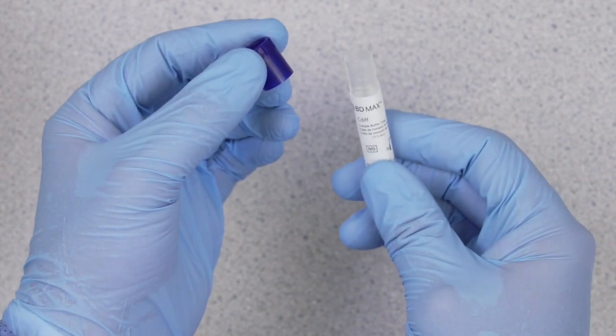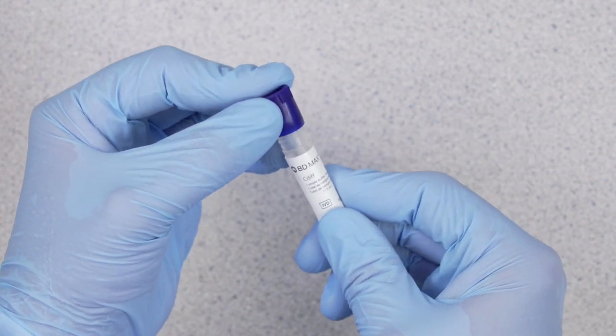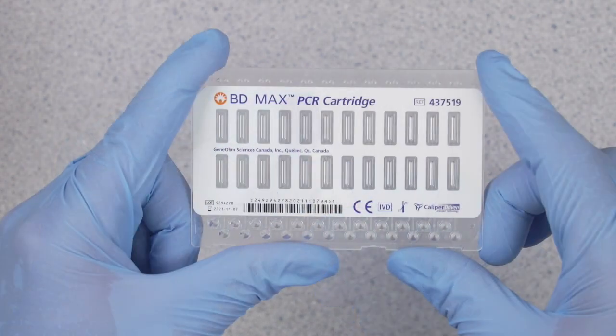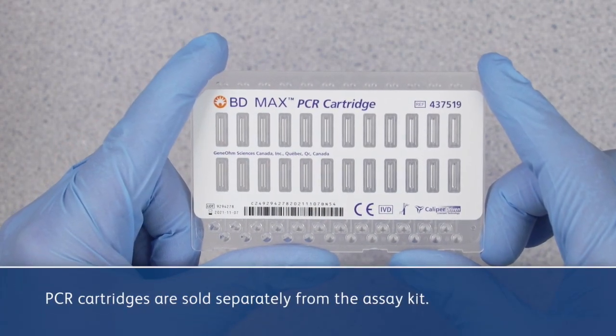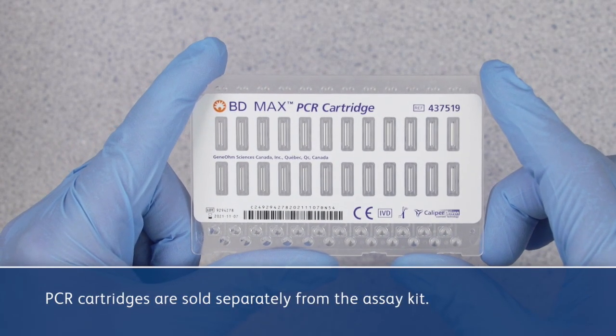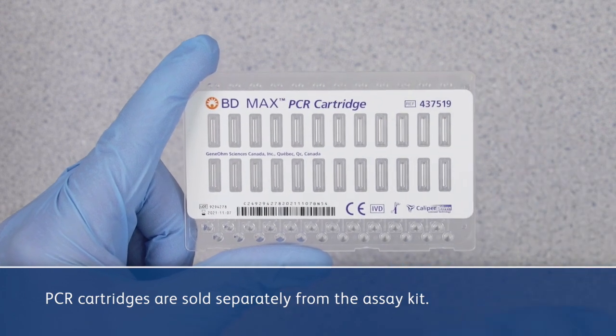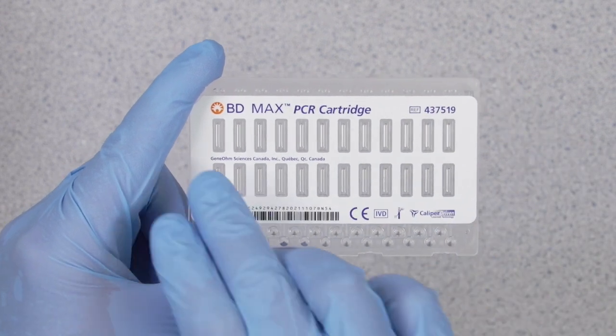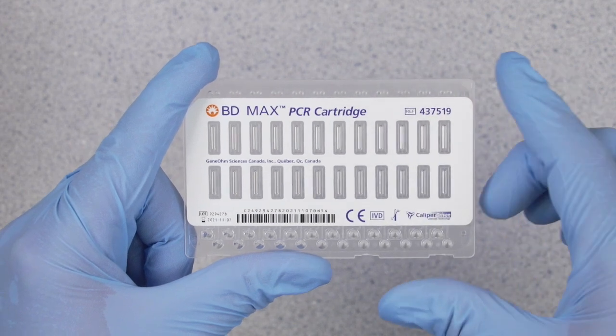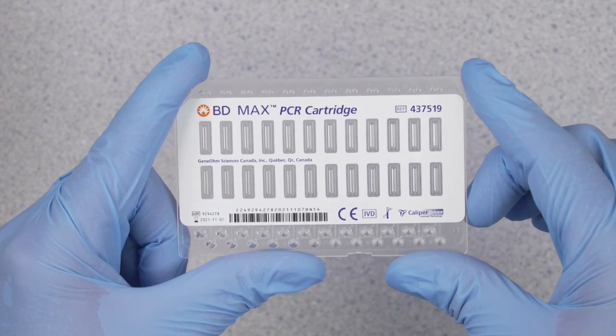Septum caps are provided to recap prepared patient samples when ready for testing. The PCR cartridge has 24 self-contained chambers for the PCR amplification and detection, 12 chambers on the bottom, and 12 on the top. It's the same cartridge the BD Max system uses for all assays.